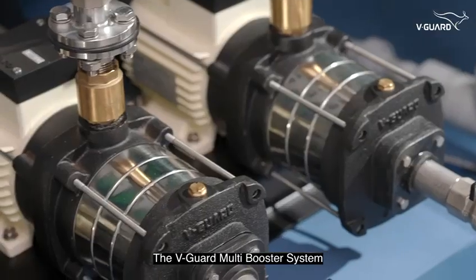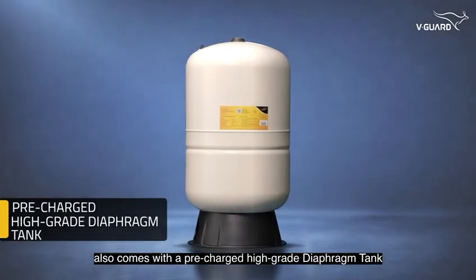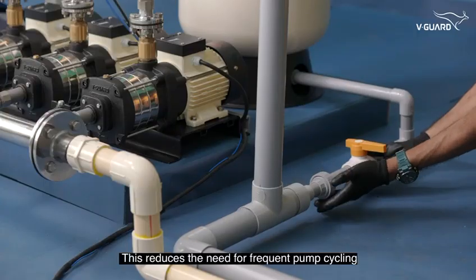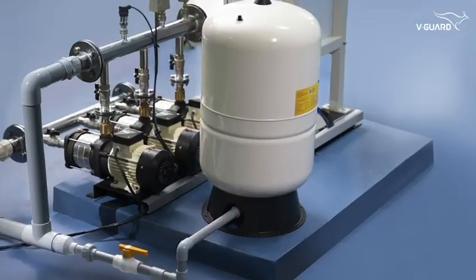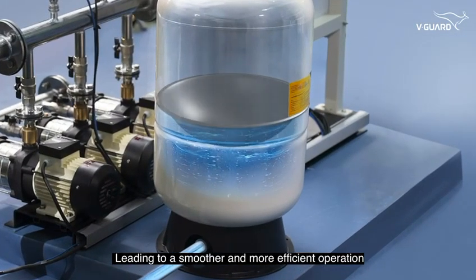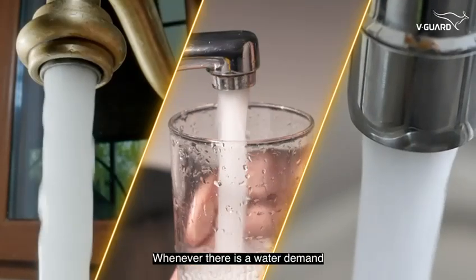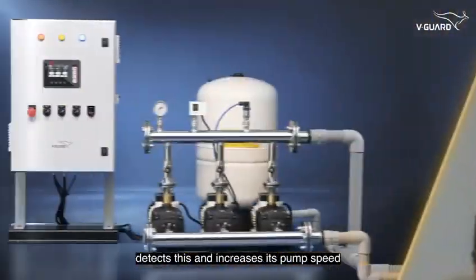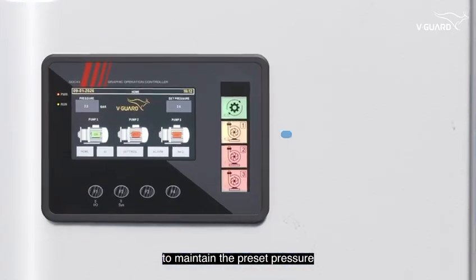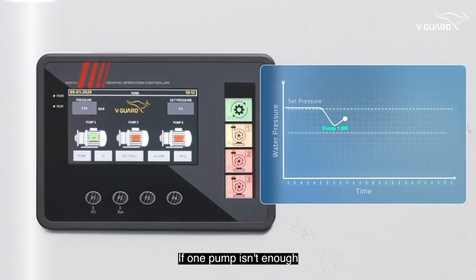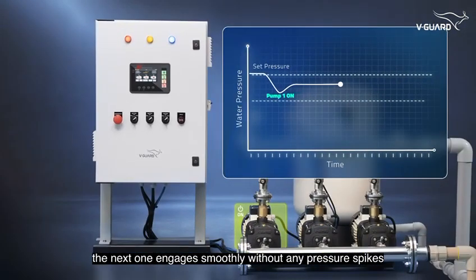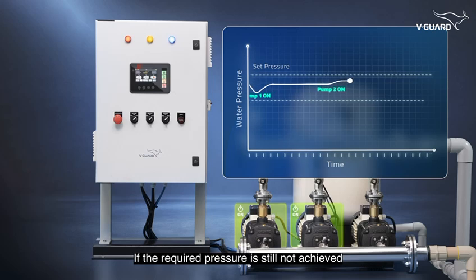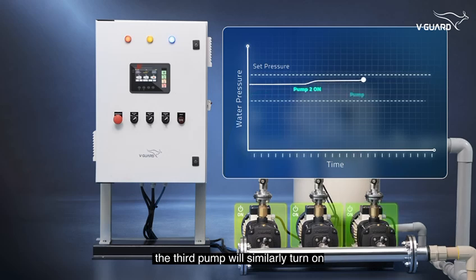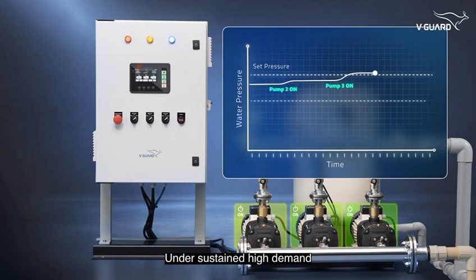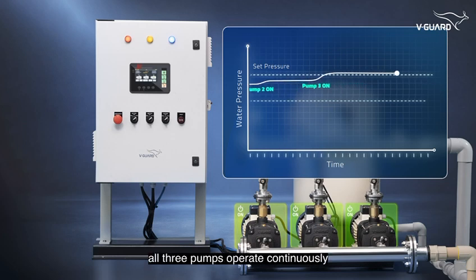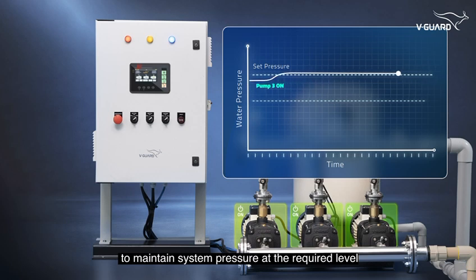The V-Guard Multi-Booster System also comes with a pre-charged high-grade diaphragm tank that stabilizes pressure. This reduces the need for frequent pump cycling, leading to a smoother and more efficient operation. Whenever there is a water demand, the V-Guard Multi-Booster System detects this and increases its pump speed to maintain the preset pressure. If one pump isn't enough, the next one engages smoothly without any pressure spikes. If the required pressure is still not achieved, the third pump will similarly turn on. Under sustained high demand, all three pumps operate continuously to maintain system pressure at the required level.